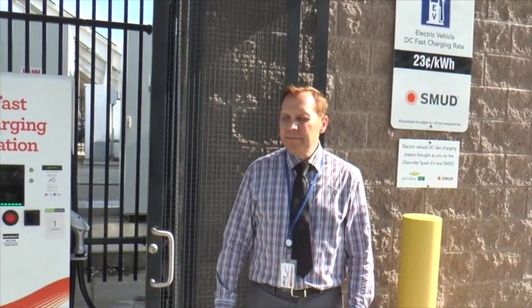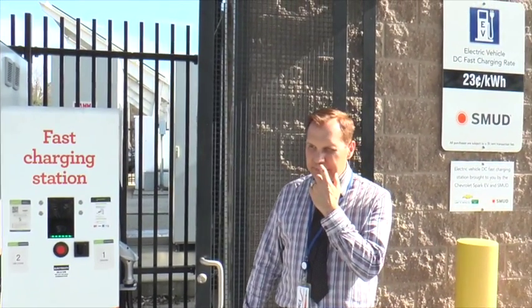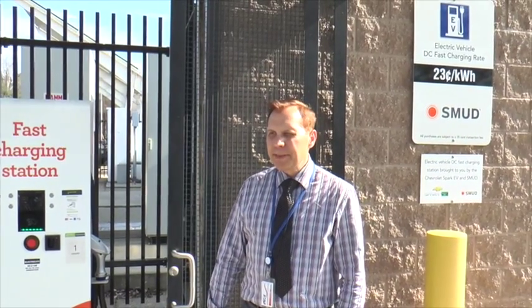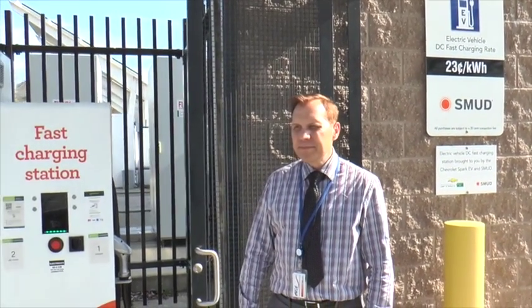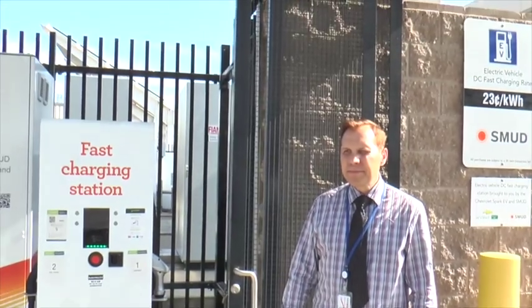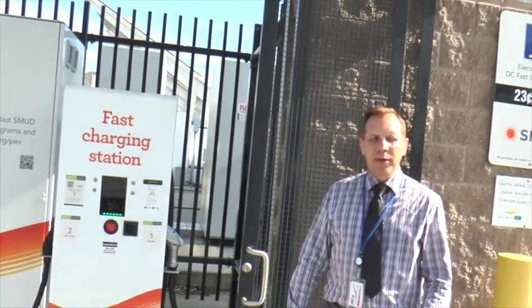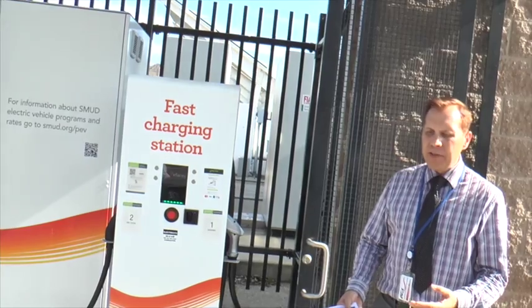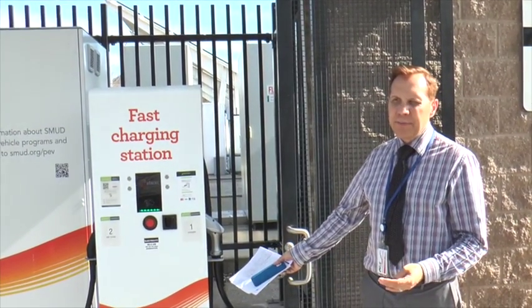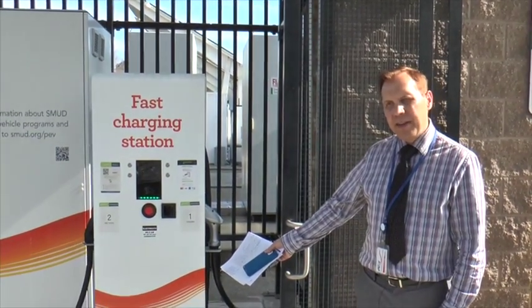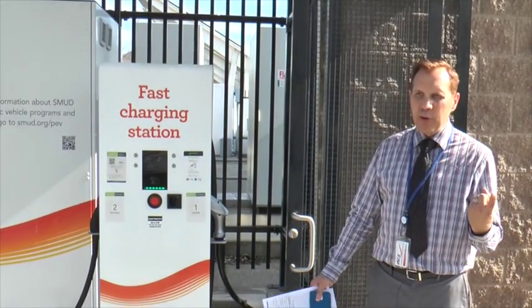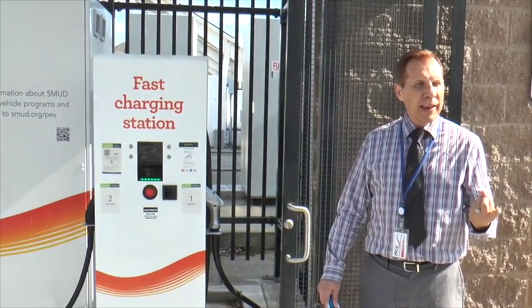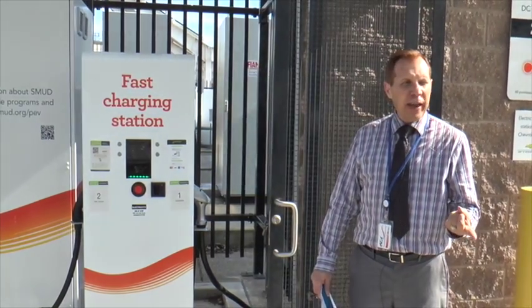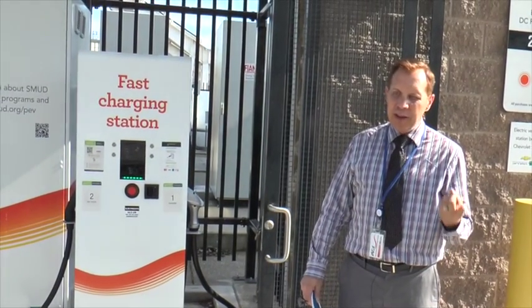Is a lot of that cost because it's a retrofit, like the trenching? If it were a new facility instead of a retrofit, would it be as costly? The question was what's driving most of the cost. The fast charger alone is $30,000, and it's a 480 feed, so that's industrial power, meaning a new service. You've got to bring in 480, and just the transformer cost me $45,000.